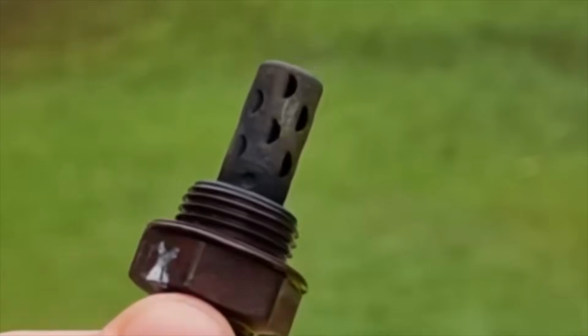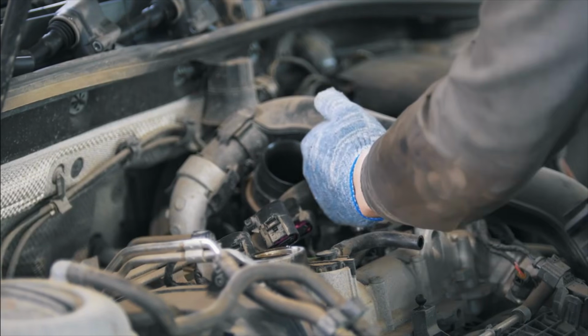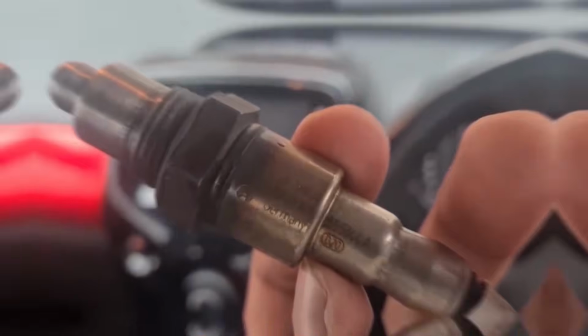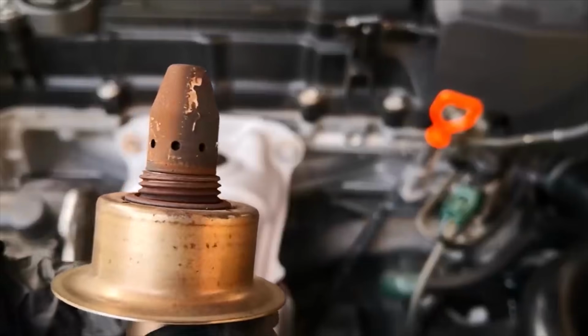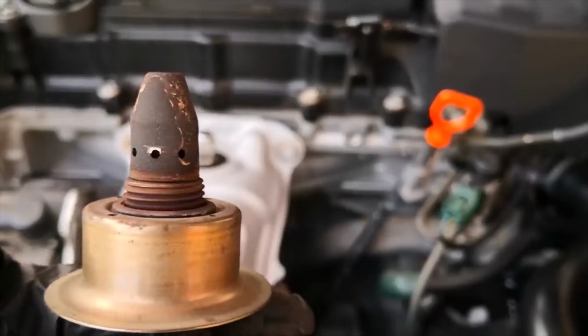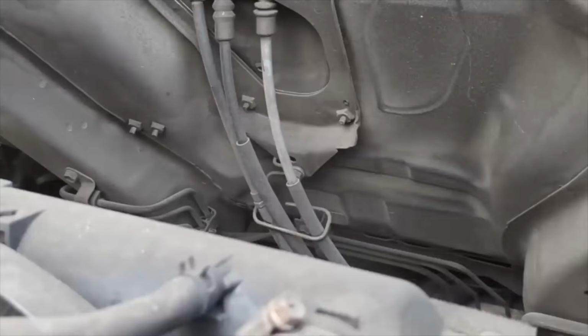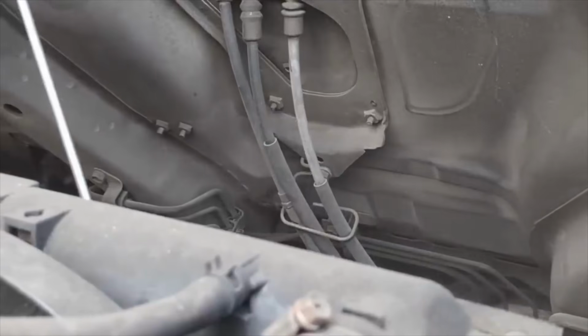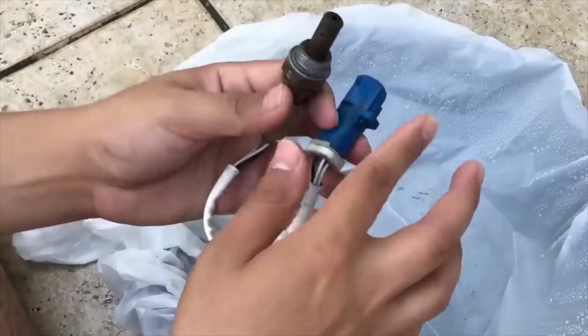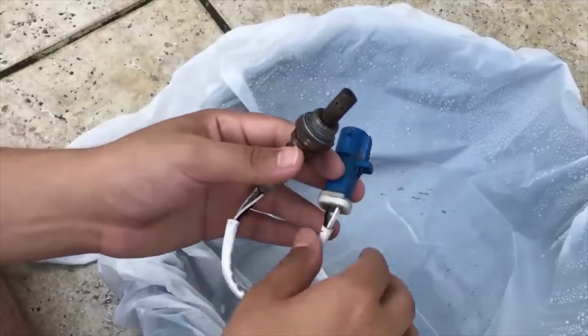Need to speed it up? Heat gun on low setting. Hold it 12 inches away. Never let the sensor surface exceed 150 degrees. I know 60 minutes feels like forever, but you just spent 30 minutes soaking it. Don't ruin it in the last step by rushing. Now that your sensor is spotless and dry, how you put it back in matters more than most professionals realize.